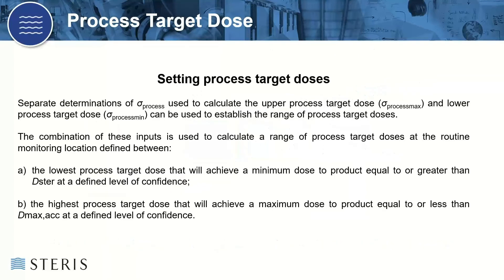Setting the process target dose involves separate determinations of process variation — sigma process — used to calculate the upper and lower process target dose and establish the range of process target doses. The combination of these inputs is used to calculate a range of process doses at the routine monitoring location. The lowest process target dose will achieve a minimum dose equal to or greater than the sterilization dose at the defined level of confidence — K equals 2, as most processes are set at 95% confidence. The highest process target dose achieves a maximum dose to product equal to or less than the maximum dose at the defined level of confidence. Basically, you're looking at minimum dose plus a certain percentage and maximum dose minus a certain percentage, and that becomes your target dose.